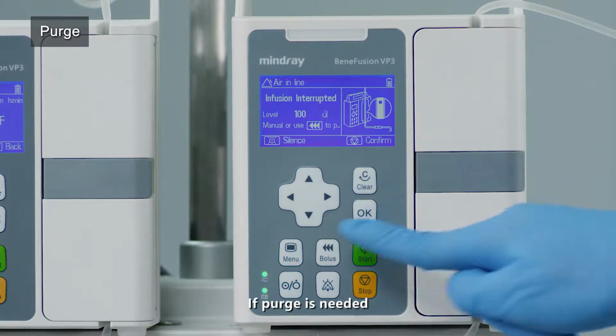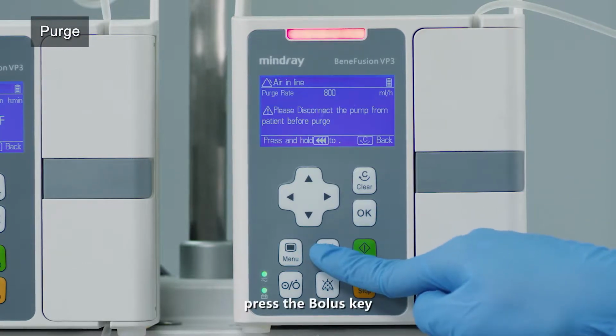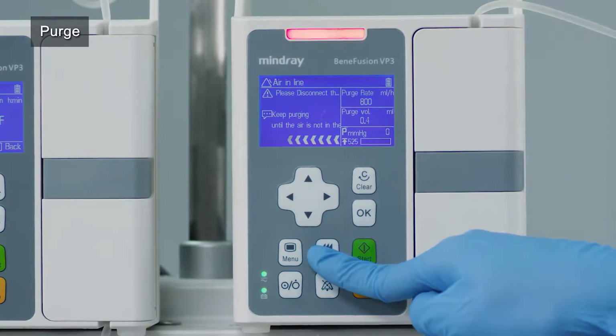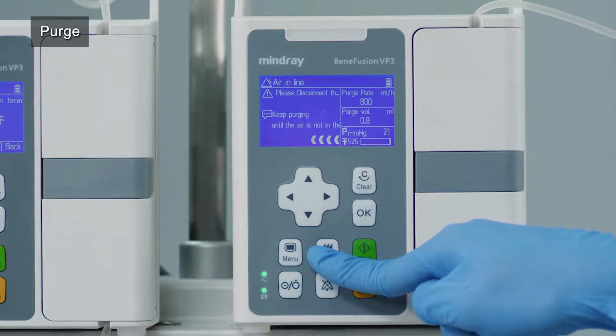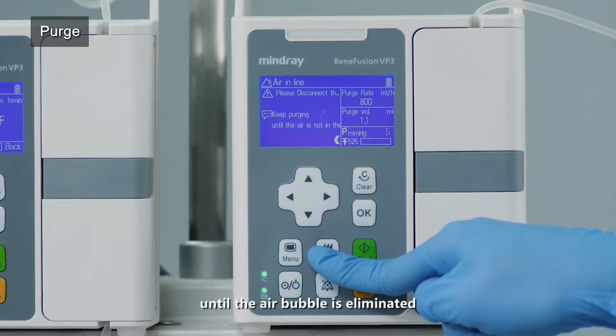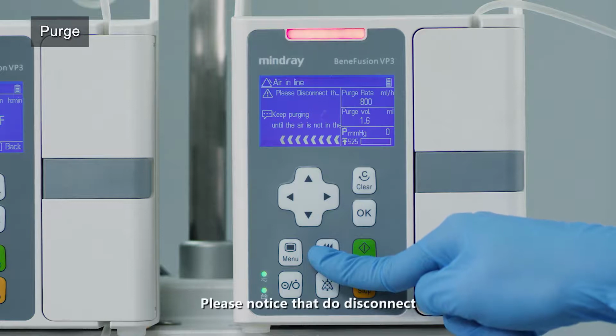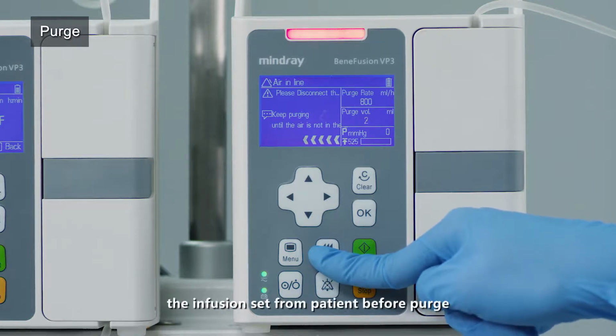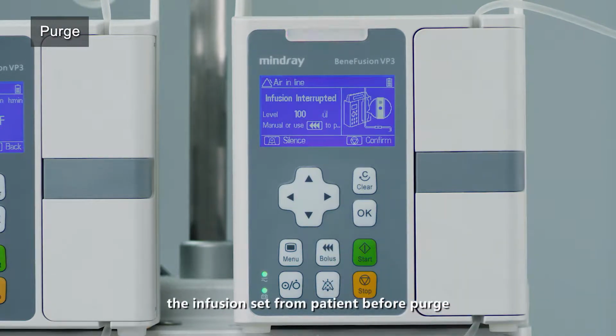If purge is needed, press the bolus key, set the purge rate, and press and hold the bolus key until the air bubble is eliminated. Please notice that you must disconnect the infusion set from the patient before purging.